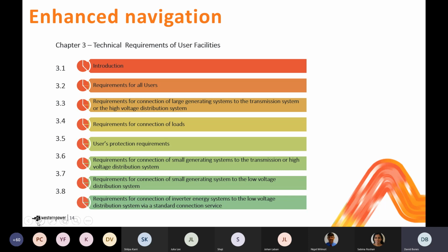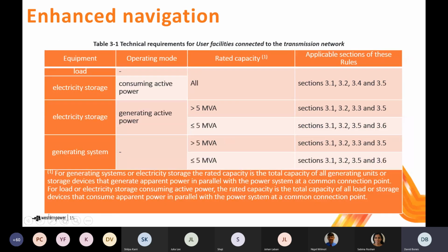I mentioned that we've done a bit of work in 3.1 to try and provide a better way of mapping the requirements for users. This slide is one of the tables that we've introduced into section 3.1. This table talks about the technical requirements that user facilities need to meet if you're connected to the transmission network. And on the next slide, we'll see there's a similar table which presents the technical requirements for user facilities connected to the distribution network.